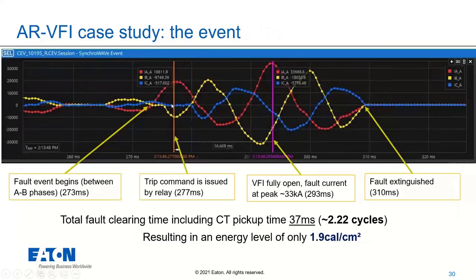So just taking a look at that fault event itself. You've got that fault event just starting right about here. You can see that the A and B phases, so our A in red and our B in yellow, take the brunt of it. C is trailing on behind. We get to our peak fault magnitude about a cycle through that, and then about another cycle or so, just a little bit over, we're actually fully cleared.